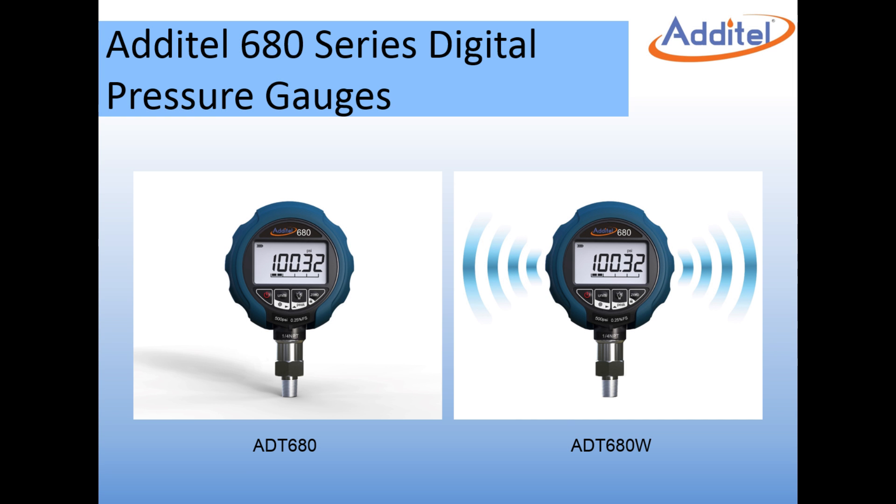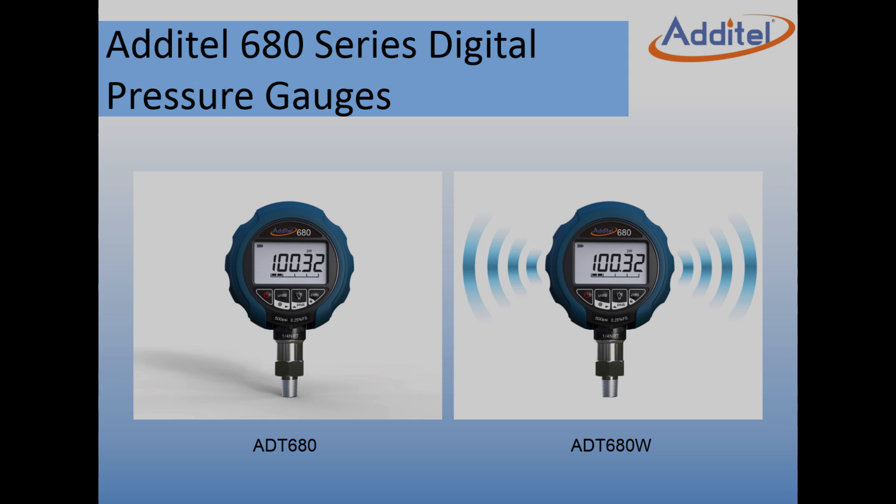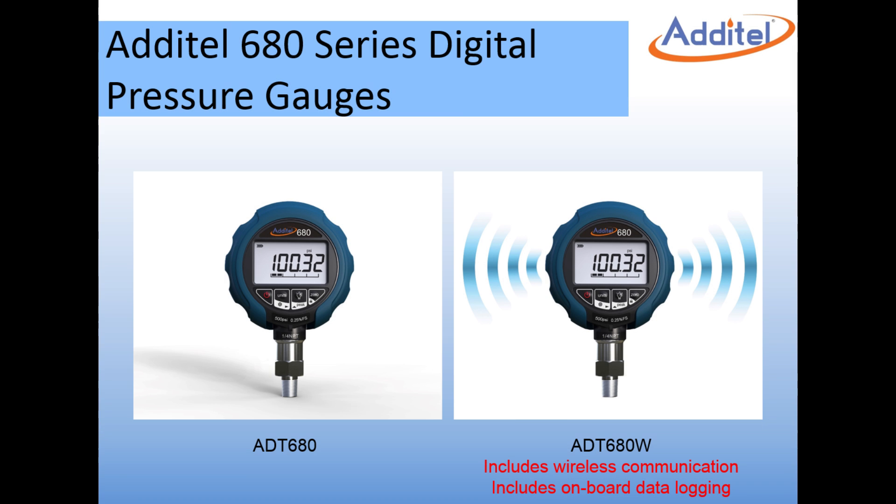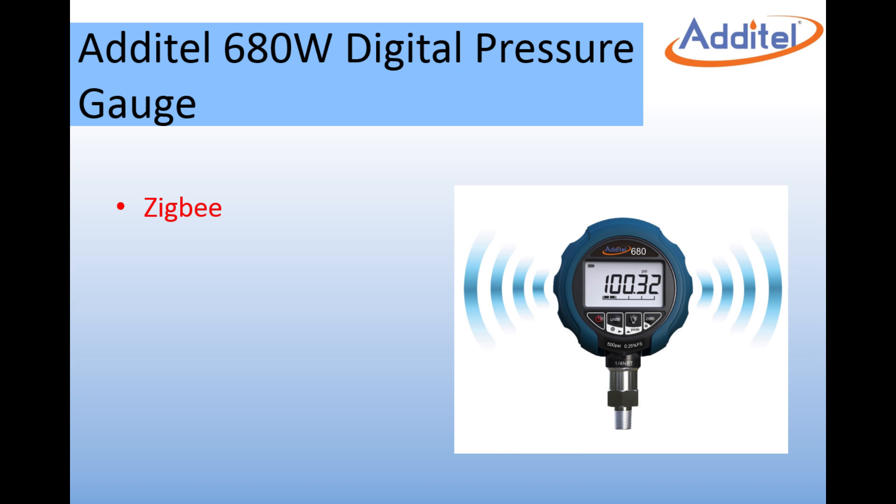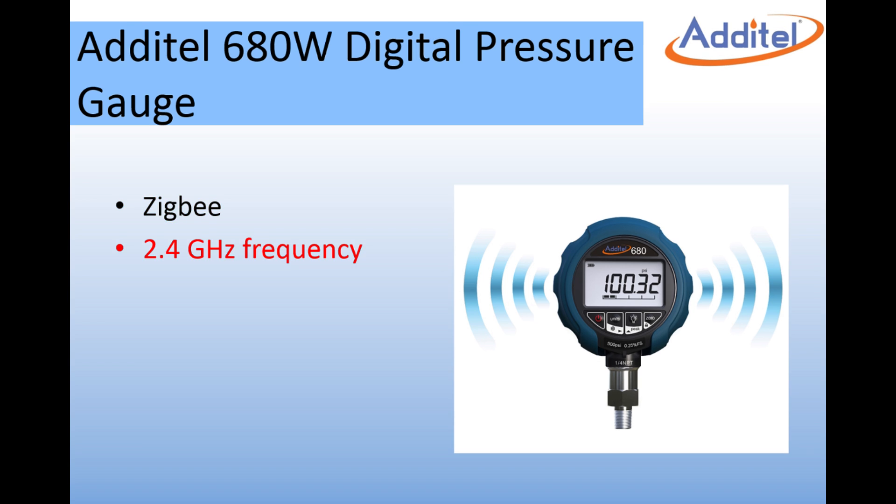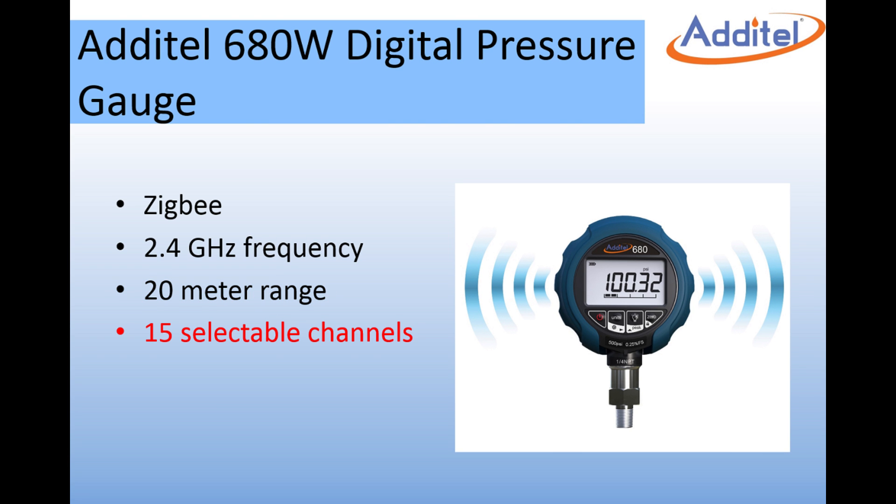The Additel 680 series digital pressure gauges each have an optional feature which includes wireless communication and onboard data logging. The model ADT-680W includes these optional features. The ADT-680W wireless communication utilizes Zigbee at 2.4 GHz. Each wireless gauge can transmit up to 20 meters and there are 15 selectable channels in which each gauge can be programmed to transmit on.